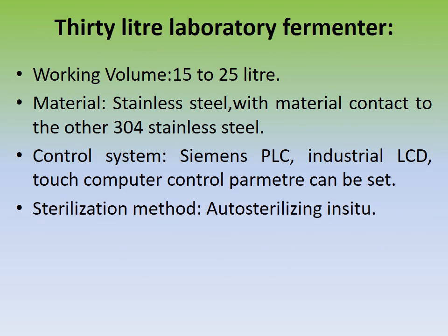Now see here the 30-liter laboratory fermenter. Its working volume is 15 to 25 liters. Okay, I think you are understanding. Here, the working volume of the 30-liter capacity fermenter is 15 to 25 liters, and it is made up of stainless steel for the material in contact. Mostly we use 304 stainless steel.